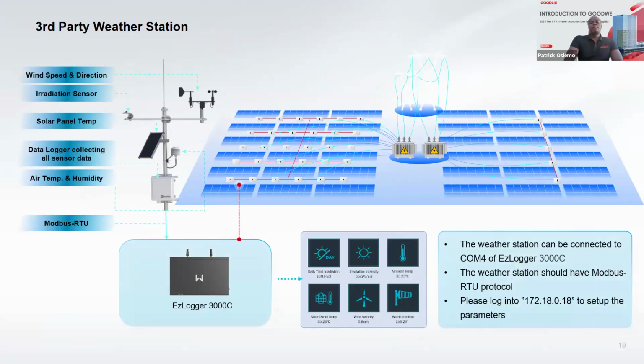Then we have compatibility with third parties. One of the third parties that GoodWe is compatible with is weather stations. As long as it's a smart weather station, that is Modbus RTU communicating, we have a number of compatible ones, so we can sense the wind speed, irradiance, temperature. All these weather conditions can be uploaded or communicated to a controller, which is the EZ Logger 3000C. And in your monitoring portal, you'll be able to get all this data that is impacting your system from the weather. And from that, you'll be able to know the performance ratio, or the performance of your plant, remotely.